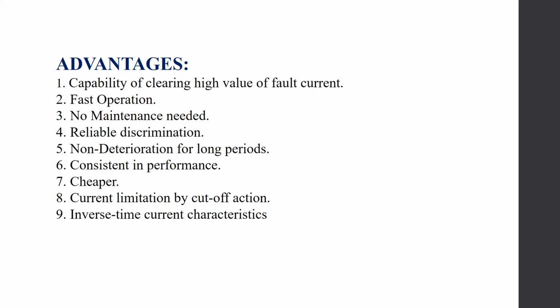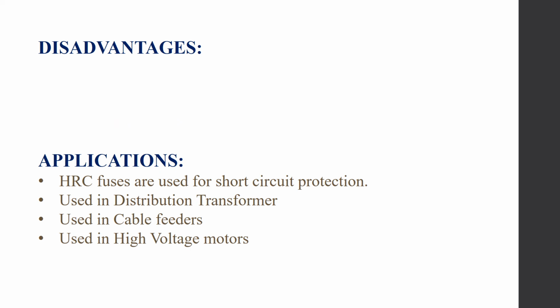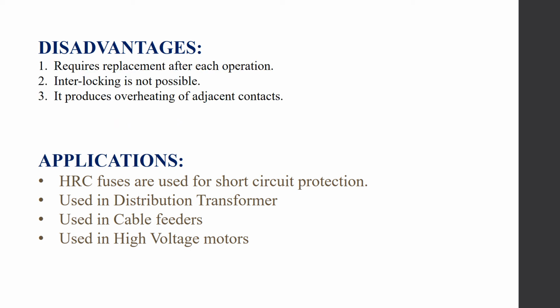Discussing advantages, these are some of the advantages of HRC fuse: it is cheaper, fast operation, no maintenance needed, reliable discrimination, current limitation, inverse time current characteristics. Talking about the disadvantages of HRC fuses, just like a normal fuse, it also requires replacement after each operation. That is, once the fuse wire is melted, then we have to replace the HRC fuse. Interlocking is not possible here. Also, it produces overheating of the adjacent contacts.